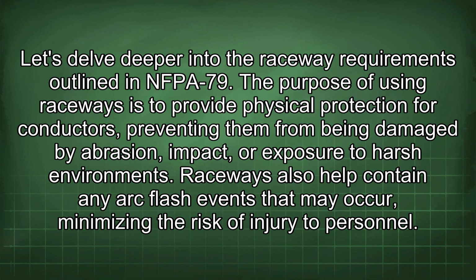Let's delve deeper into the raceway requirements outlined in NFPA 79. The purpose of using raceways is to provide physical protection for conductors, preventing them from being damaged by abrasion, impact, or exposure to harsh environments. Raceways also help contain any arc flash events that may occur, minimizing the risk of injury to personnel.